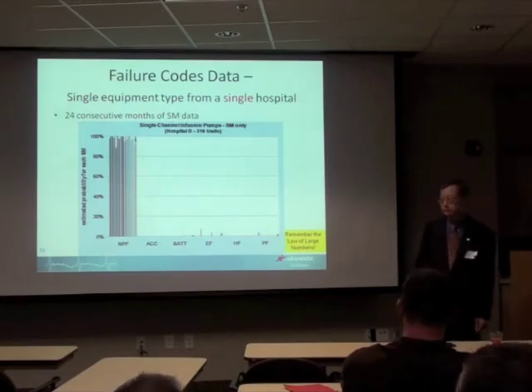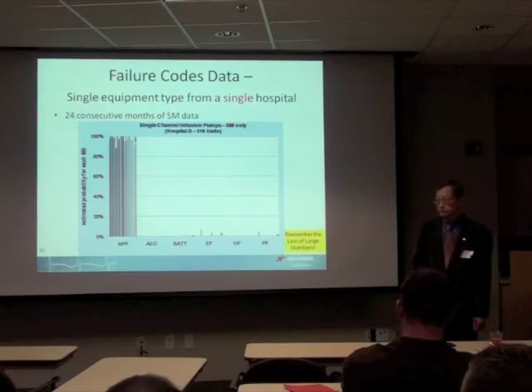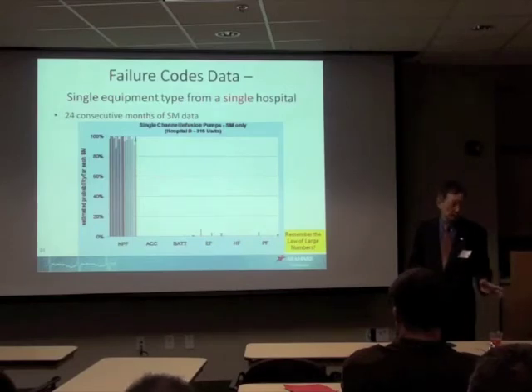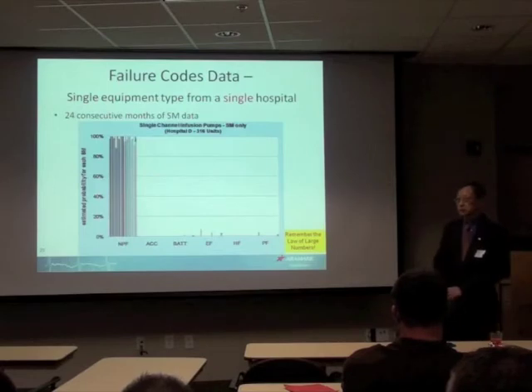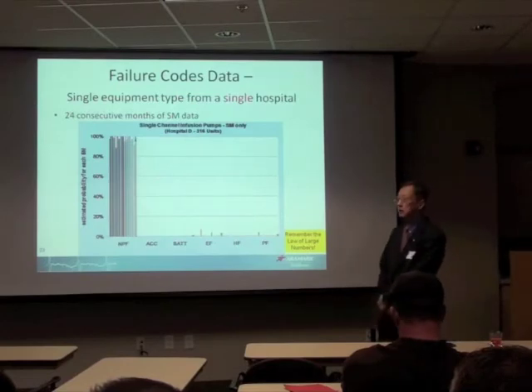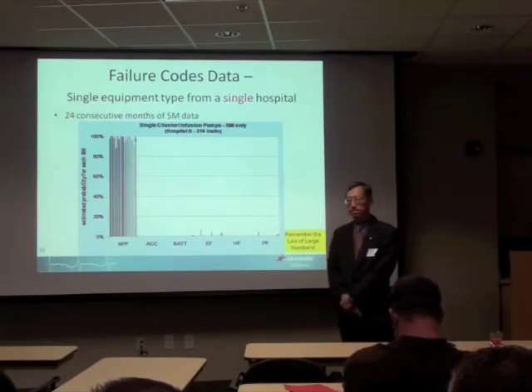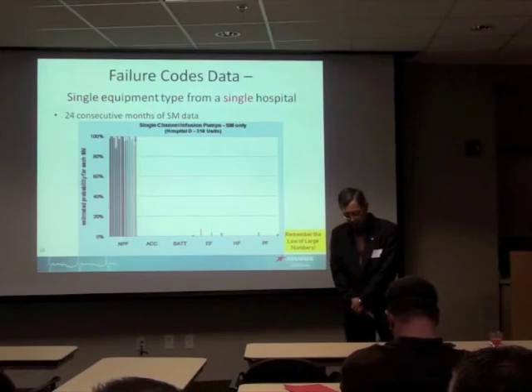It may not necessarily be that it was a battery failure. It failed because of the battery, because the battery was dead, because they didn't plug it in. That doesn't necessarily mean you had to replace the battery. Well, I guess I need a little more definition. To me, that would not be a battery failure, that would be a use failure where the operator didn't keep the pump plugged in.